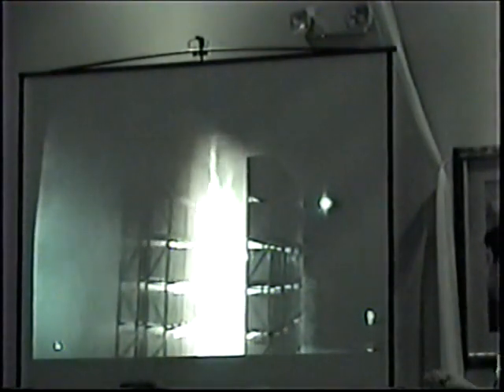Control those sprinklers. Doesn't jump to the target array. Doesn't travel out to the ends of that. Push down too quick. Usually when you see this phenomenon, this smoke getting driven down and the visibility going before, that means you've pretty well got the test under control. When it stays real bright, it tends to be indicative of potential failure. So control those sprinklers, visibility.